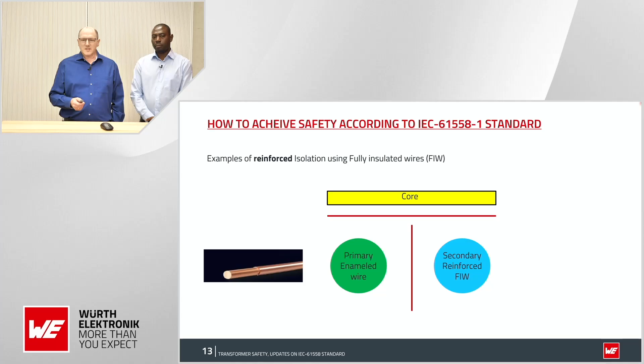The red lines are barriers designed for basic insulation, and they need to withstand the requirements of basic insulation. You can see here the primary is enameled wire, and I have a picture showing it directly, and the secondary is a fully insulated wire. With this construction, which is normally a standard construction, we can get a reinforced design like Antwi explained before.